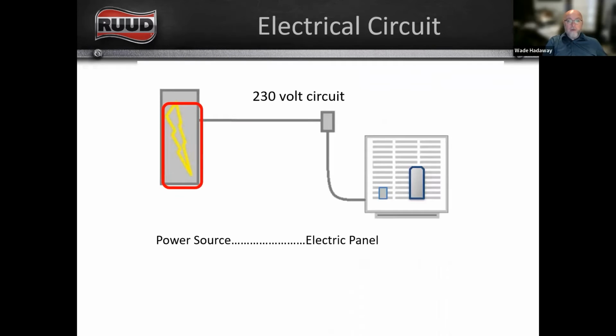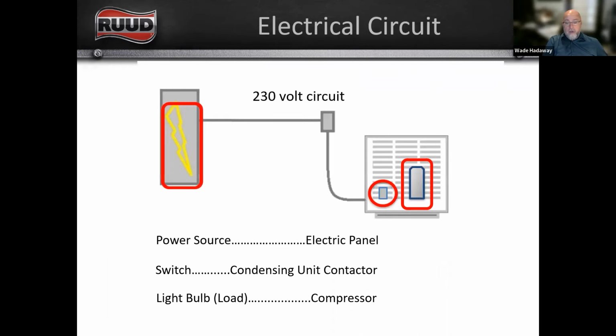The same way that we have an electrical circuit on an outdoor unit, a condensing unit, right? Our power source is the panel or the disconnect. Our switch is going to be the contactor inside our condensing unit. And then our load, or the light bulb in this case, is going to be the compressor and/or fan motor, or whatever else is in this outdoor unit, right? What other line voltage components are in this unit?